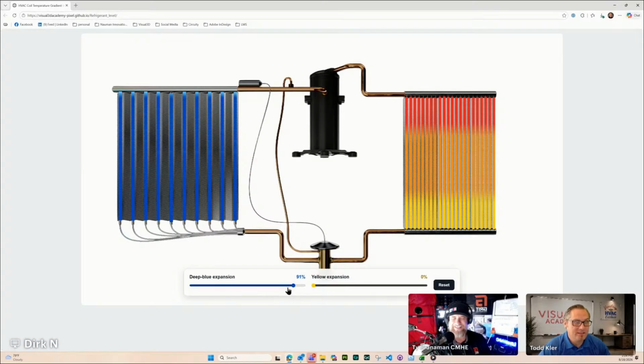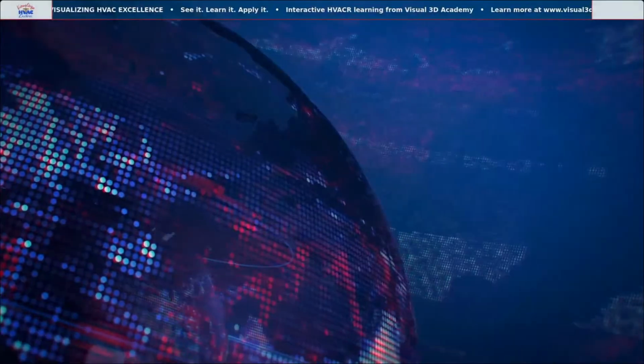and we don't want to do that, because I just watched a video of yours the other day where you open up a compressor and see it copper plated, with all those issues that come with overcharging and washing out the oil.